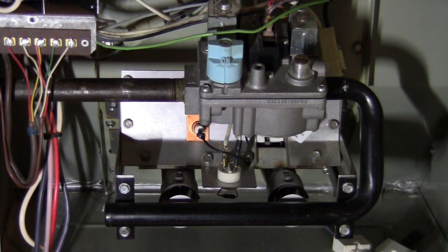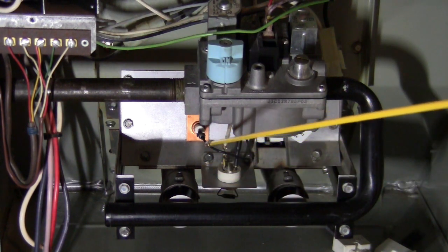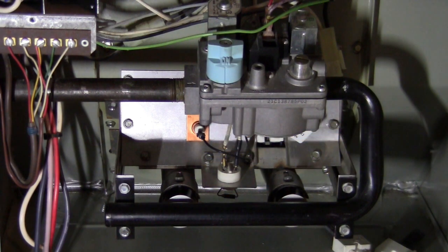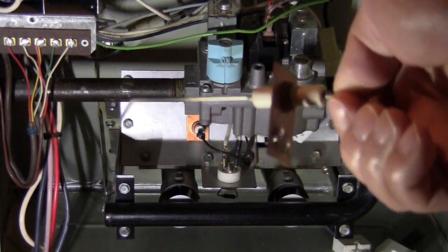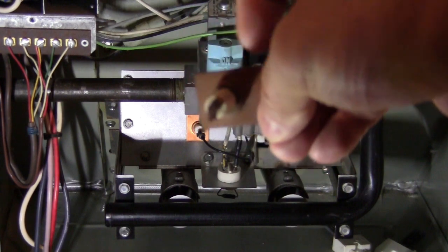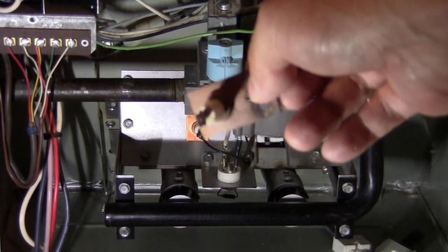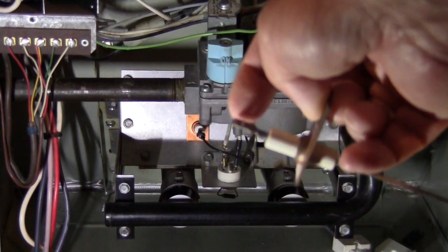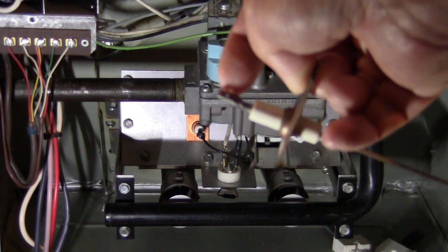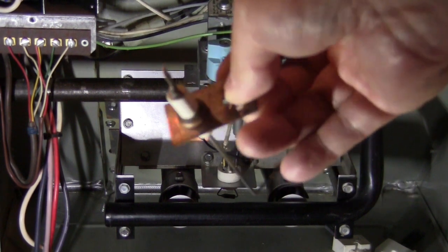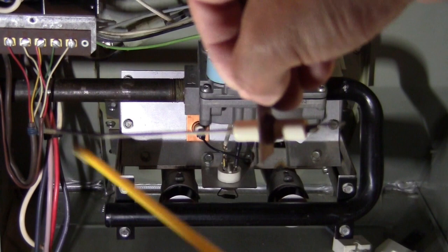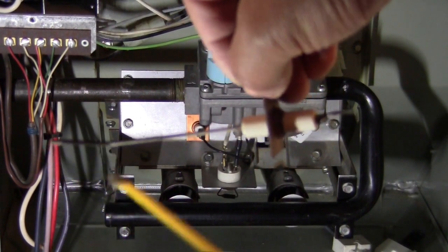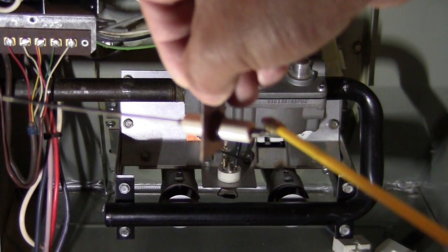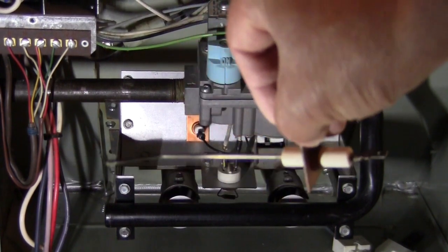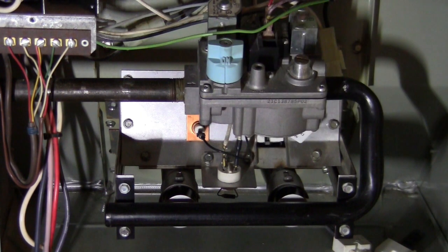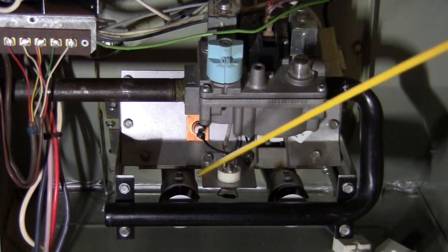Oh, I almost forgot one of the most important sensors in this furnace. It's the flame detect sensor over here. It looks like this. See that? It's very simple. The outside metal connector mounts it to the metal case, and this is the sensor. I don't know if it's a positive and negative lead, but actually there are two leads over here, right? So once the fire burns on this body, it doesn't matter whether it's the tip or the body, it sends a signal to the controller. It says, oh, I see the fire. When it sees the fire, that means the gas is burning in the burner inside.